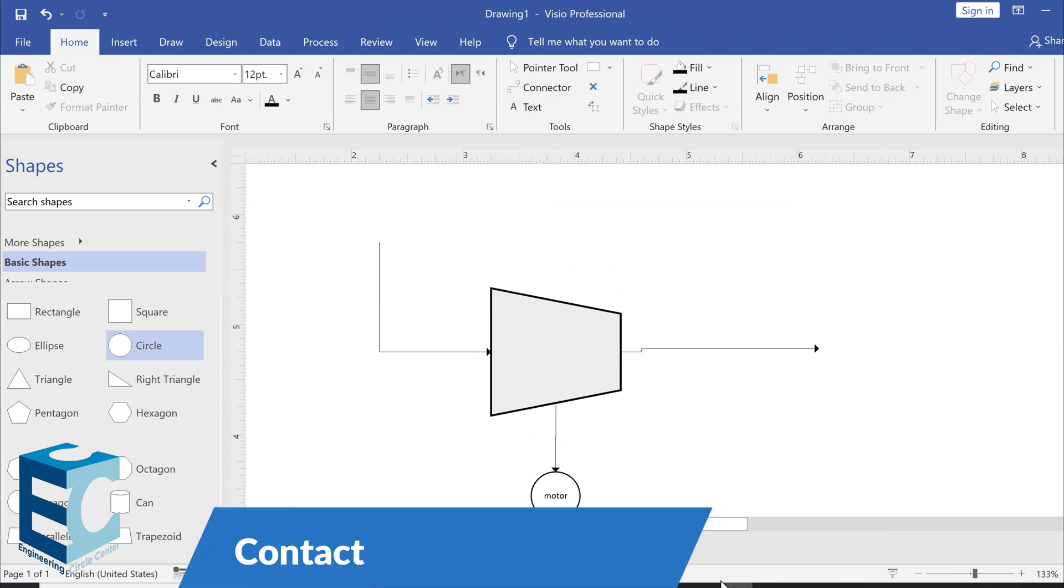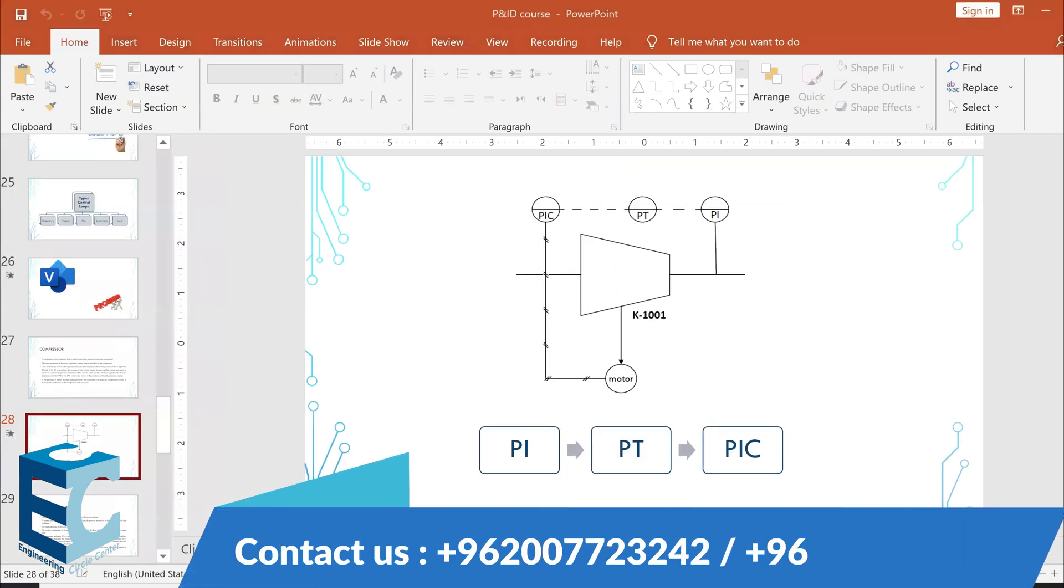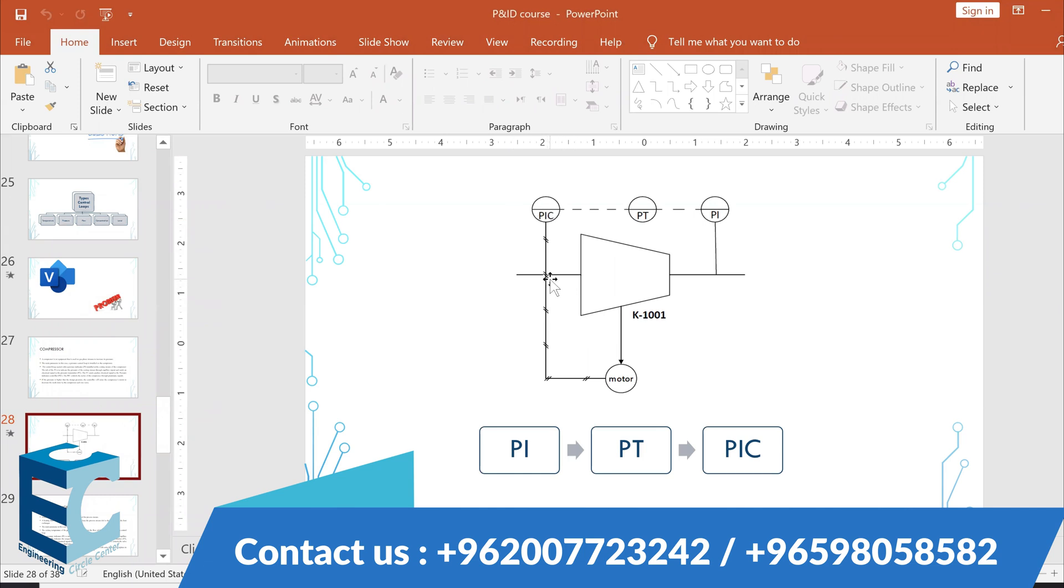Now, if you look, if you take a look at the P&ID, what's the control loop? What is going on with the compressor? The compressor, we're looking at the main variable, which is obviously the pressure. So, we need the pressure indicator, pressure transmitter, and pressure indicator and controller. That goes on to the motor.